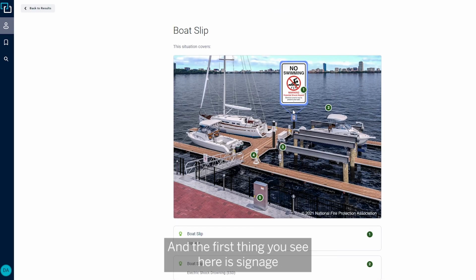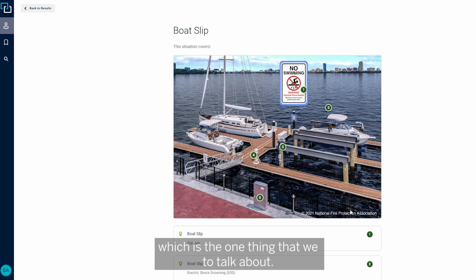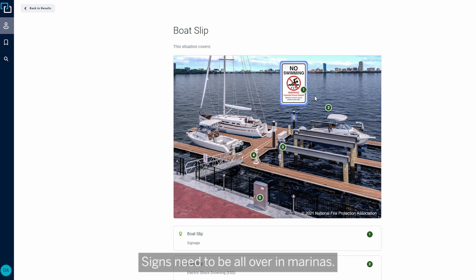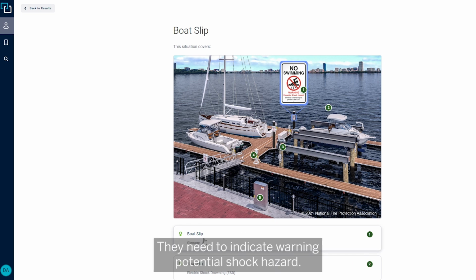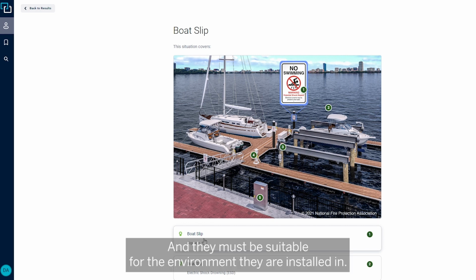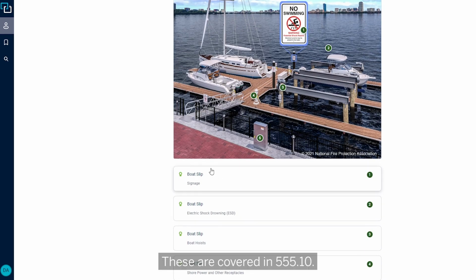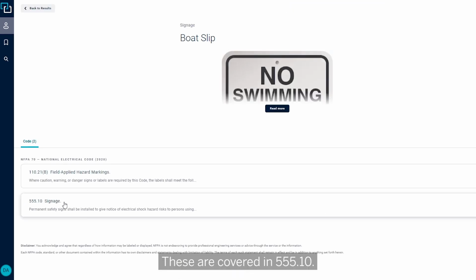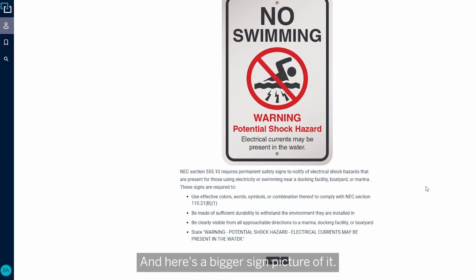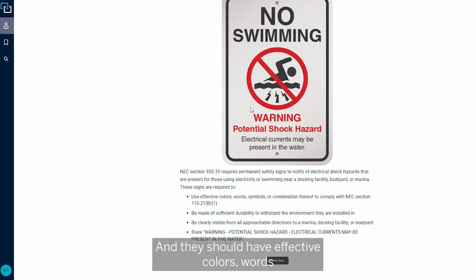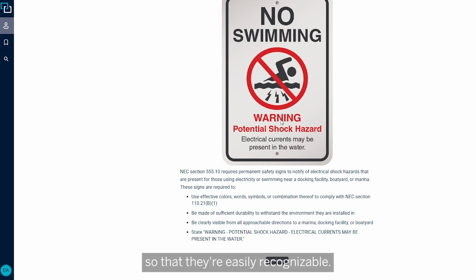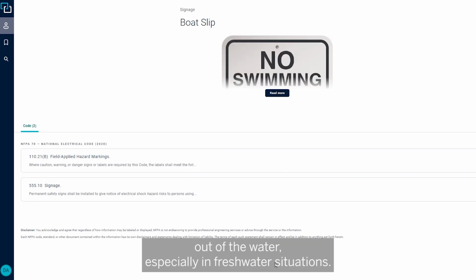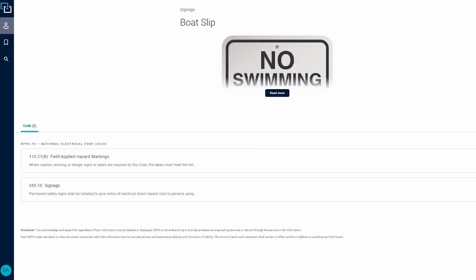You will see we have a picture, and the first thing you see here is signage, which is the one thing that we want to talk about. Signs need to be all over in marinas. They need to indicate warning, potential shock hazard, electric current may be present in the water. And they must be suitable for the environment they are installed in. These are covered in 555.10. And here's a bigger sign picture of it. And they should have effective colors, words, so that they're easily recognizable. This is an aid to try to keep people out of the water, especially in freshwater situations.